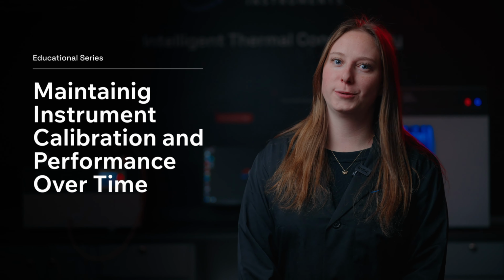Accurate and trustworthy thermal testing doesn't just depend on high-quality instruments, it depends on how well those instruments are maintained over time. Even the most robust systems can experience gradual changes in performance due to normal aging, repeated thermal cycling, environmental shifts, mechanical handling, or software and firmware updates. These changes often are subtle, and they can go unnoticed until results begin drifting outside expected ranges.